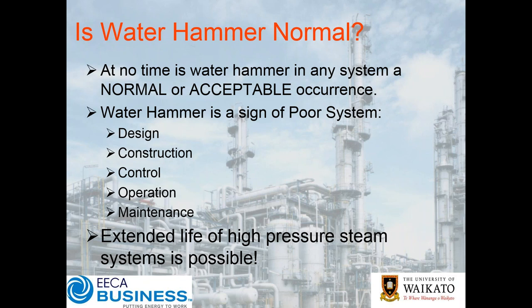Water hammer is a sign of a poor system — be it through design, incorrect construction, improper or unoptimized control, an operational issue, or a maintenance issue. I hear a lot of people talking about maintenance of high-pressure steam systems, and the number of sites around the world that have regular annual maintenance spends on reconditioning valves, control valves, traps, and other bits and pieces. The reality is all of that equipment can have a substantially extended life beyond annual expenditure — it comes back to getting things installed, operated, and maintained correctly.